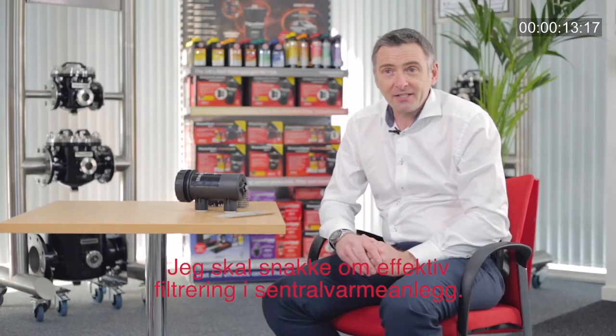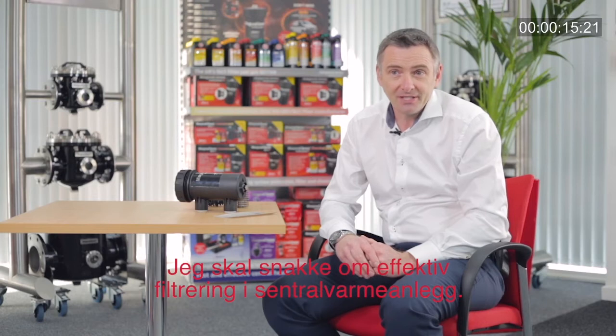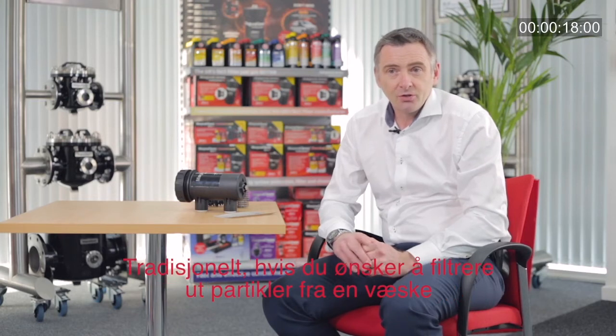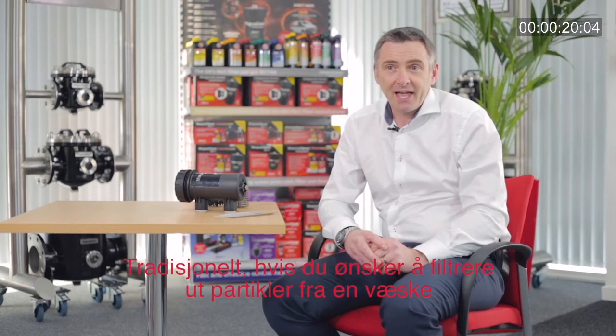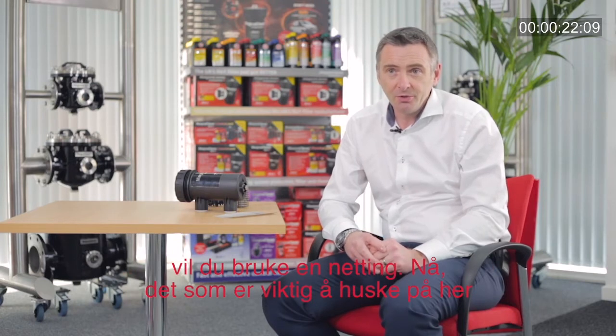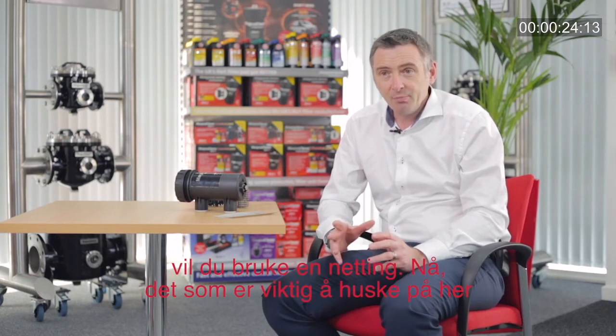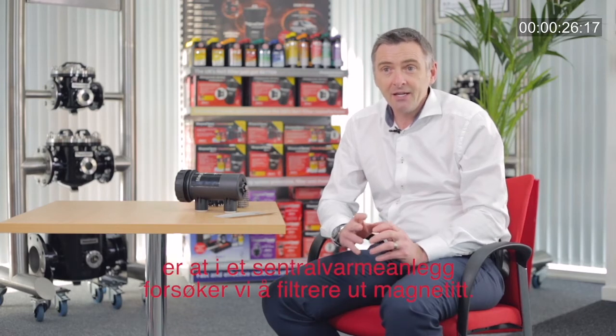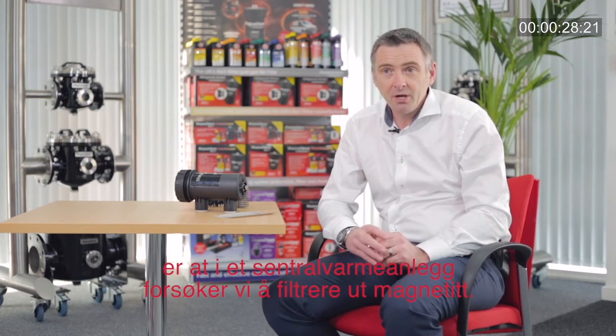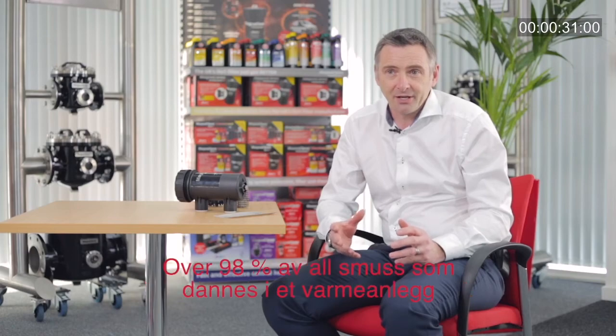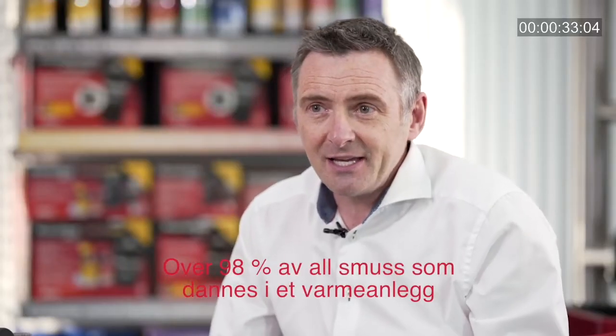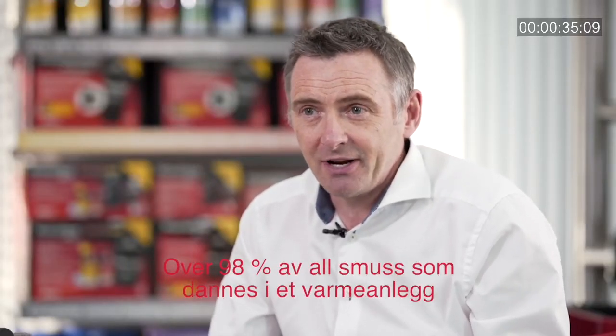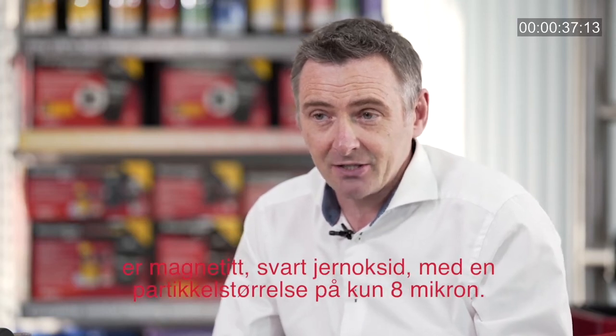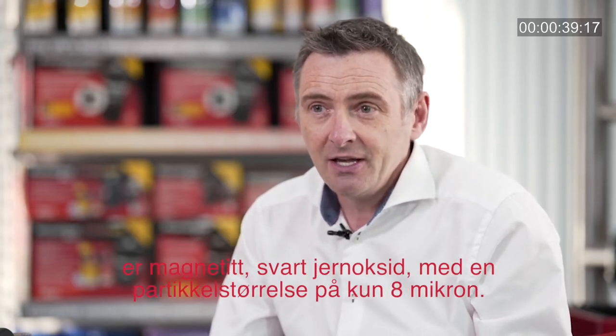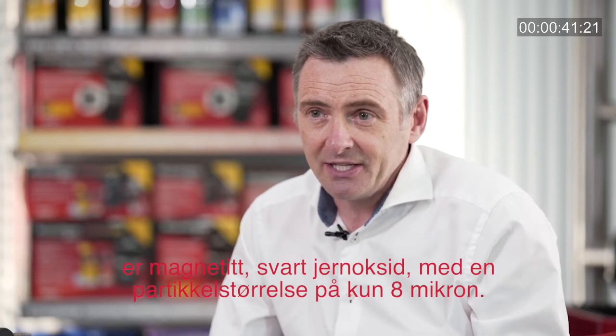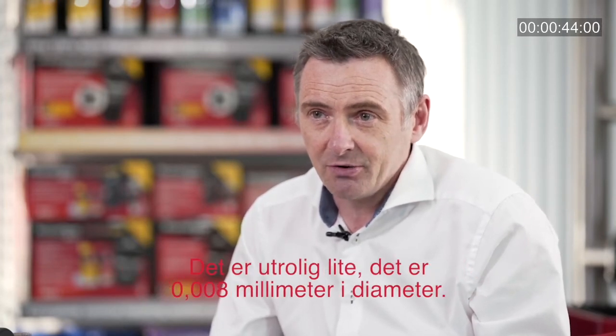I'm going to talk about effective filtration within central heating systems. Traditionally, if you want to filter any particle from within a fluid, you would use a mesh. Now, the important thing to remember here is within a central heating system, we're trying to filter out magnetite. More than 98% of all of the debris that's generated within a heating system is magnetite, black iron oxide, and the average particle size is only 8 micron.